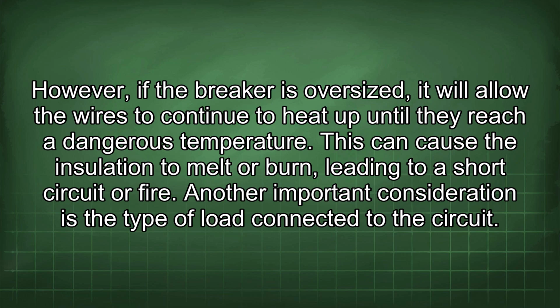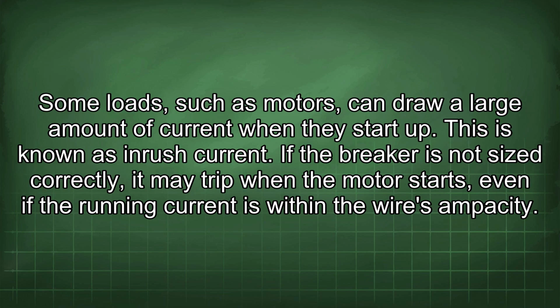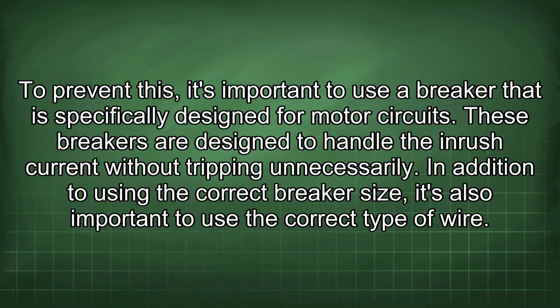Another important consideration is the type of load connected to the circuit. Some loads, such as motors, can draw a large amount of current when they start up. This is known as inrush current. If the breaker is not sized correctly, it may trip when the motor starts, even if the running current is within the wire's ampacity. To prevent this, it's important to use a breaker that is specifically designed for motor circuits. These breakers are designed to handle the inrush current without tripping unnecessarily.